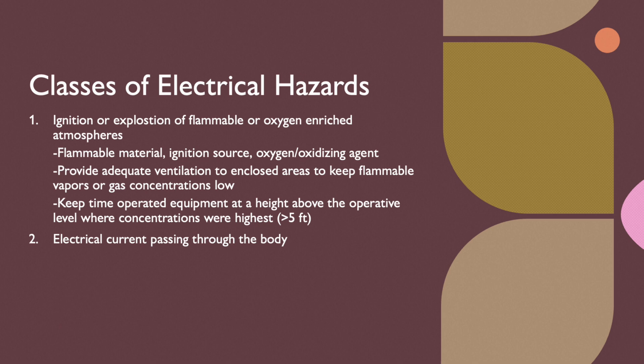You can prevent these disasters by having good airflow to keep fumes from things like acetone or collodion out of the environment, since both are combustible. You can also keep certain equipment at least 5 feet above the operating level to isolate the two volatile components, gas and machinery, keeping them in semi-different environments.